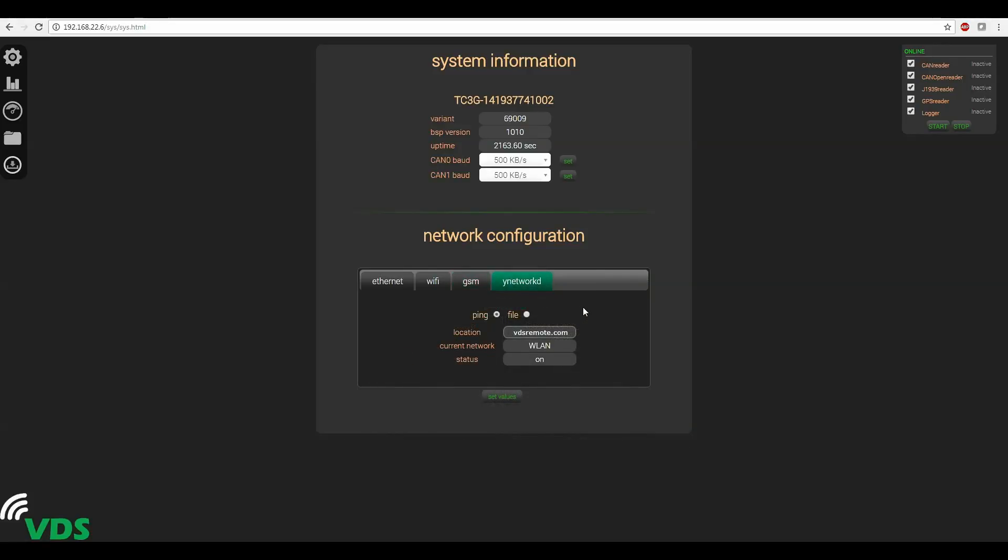Lastly, the Y network D tab is available if you're using GSM or if you're using Wi-Fi and client mode. When the ping option is set, you can use this location entry which is a website address preferably vdsremote.com to have the TC3 determine if it has an active connection. Right now it is able to connect to vdsremote.com so it's showing that its current network connection is WLAN and its status is on. You can also choose file if you'd like to connect to a specific location at that URL something like index.html. Don't forget to set your values when you change any of these settings.